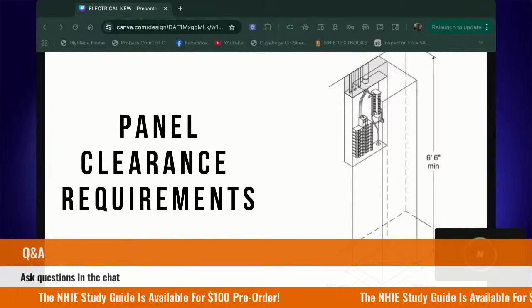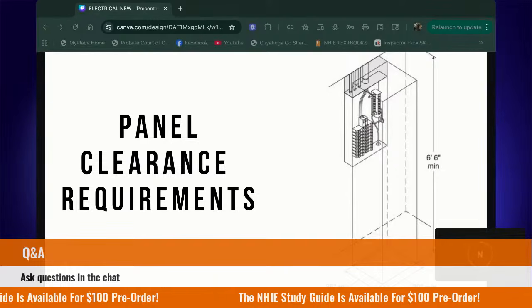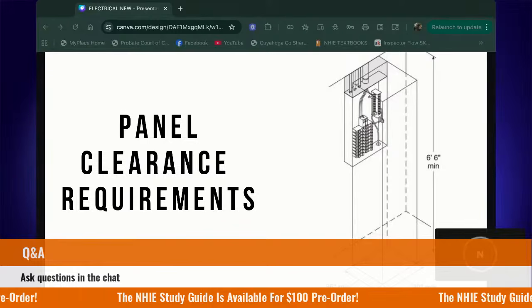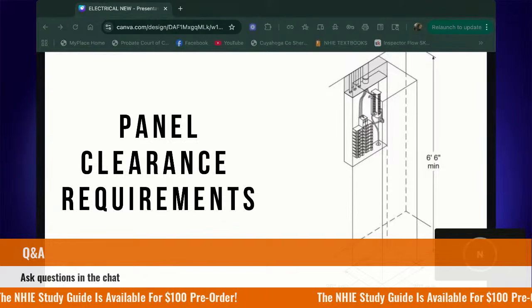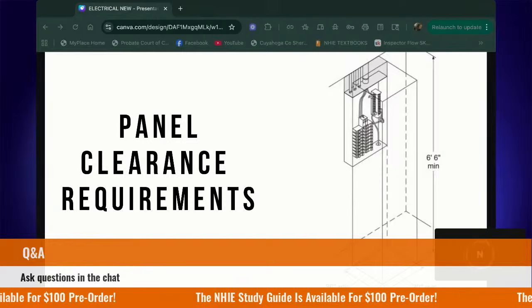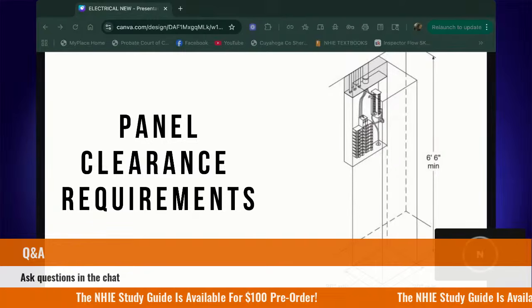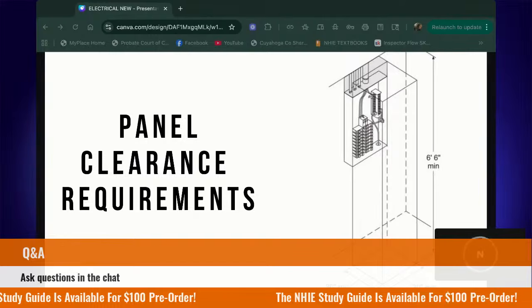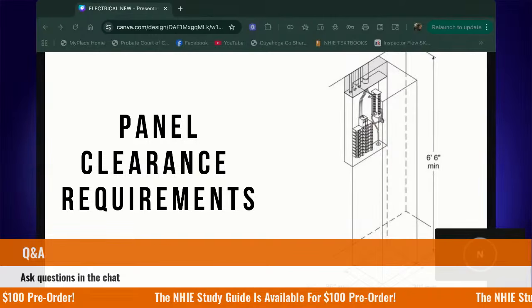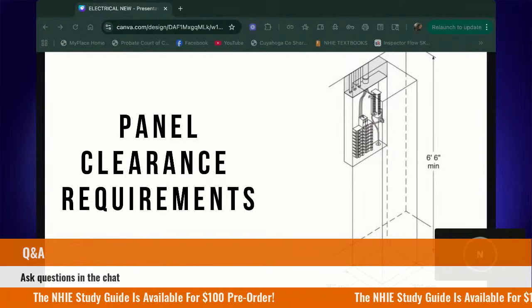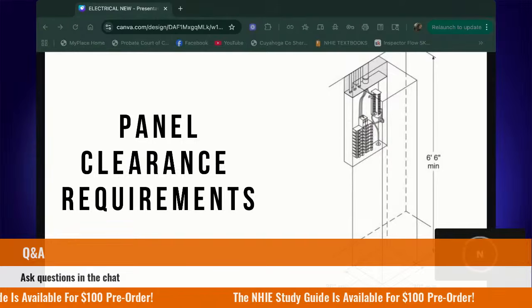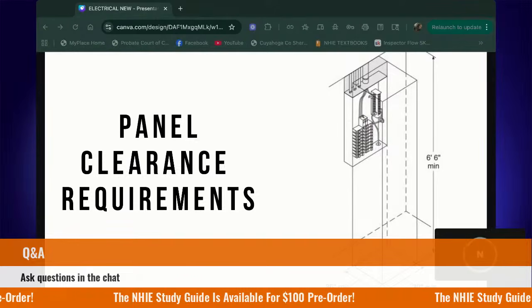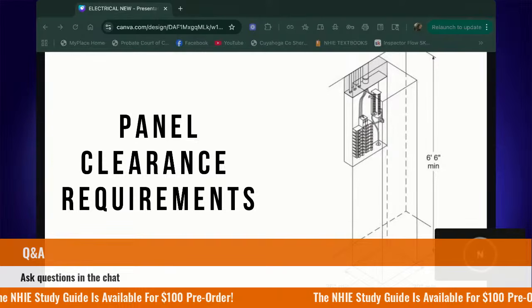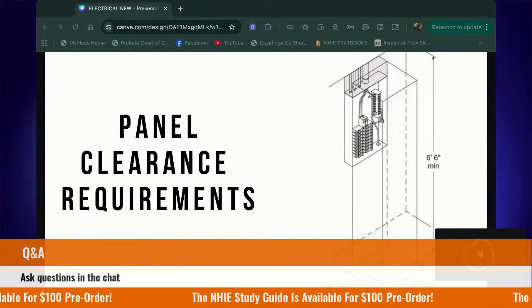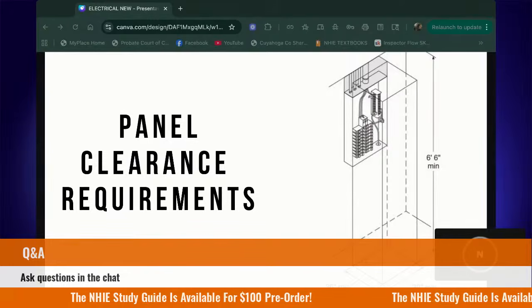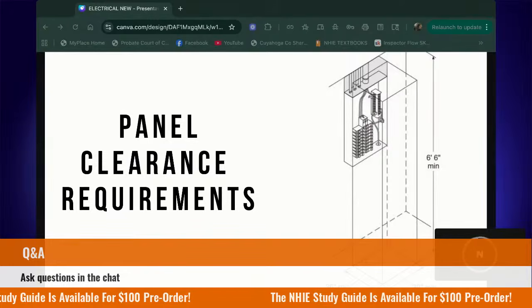So I will say this. When it is safe to open a panel, you should open a panel, because to your point, you can't assess the wiring or anything, the grounding, anything, unless you open a panel. By open a panel, we mean removing the dead front. So if it is safe for you to do so, you should do so. However, if there is any condition that makes it unsafe, then you should not, and you should document your decision if you decide not to open it.